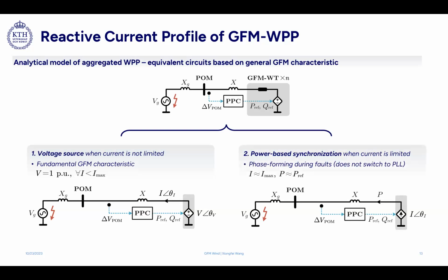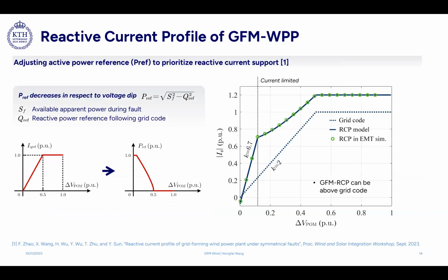Here, we don't want to switch the grid-forming wind turbine to a grid-following wind turbine by using the PLL. We just want to keep the power-based synchronization. In that sense, we have to adjust the active power reference to be sure we are able to meet the reactive current injection requirement. So here, this is the original grid code requirement based on different remaining voltage and voltage drop. We can see how much reactive current we should inject.